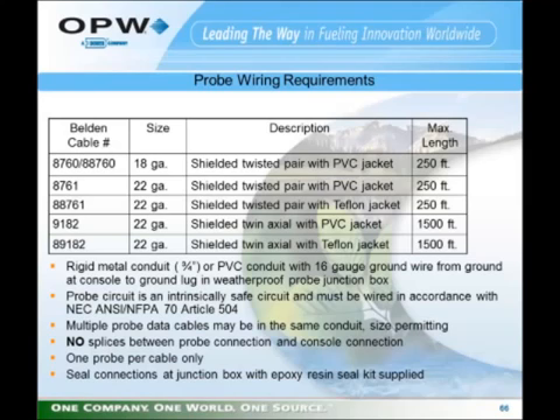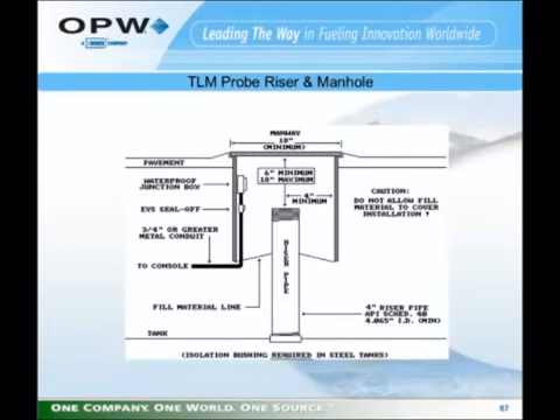Each probe cable from the probe connection cable that is attached to the probe head to the junction box, from that point back to the TLM interface module, must be what is called a home run with no splices. Only one probe can be connected per cable, and the connections for the probe in the junction box at the tank should be sealed with an epoxy resin seal kit. What we illustrate here are just the general measurements normally used to make sure that you have enough clearance between the probe riser from the tank and any manhole and junction box that may be installed over that opening. You want to make sure that you have adequate clearance so that the probe can be installed and removed and wiring can be installed and checked when needed.